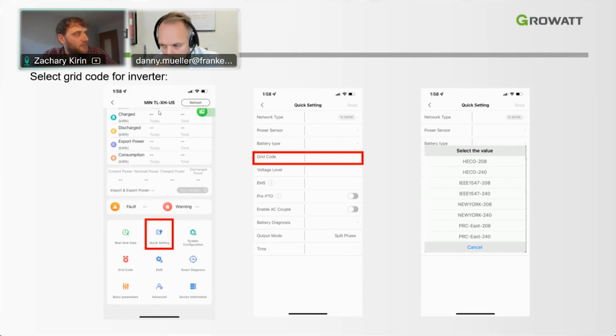Next, once the network has been configured and the inverter is connected to the internet, we will go through the quick settings, select a grid code for the inverter. And this will be based on the municipality you're a part of. If there's any grid codes that you may need exactly for the system, they can be set here. I recommend just using IEEE 1547-240. For most scenarios, this is the inverter setting that we utilize.